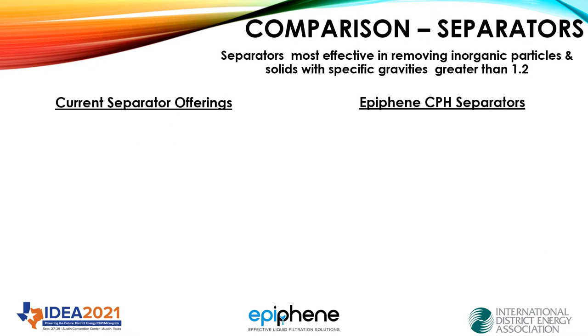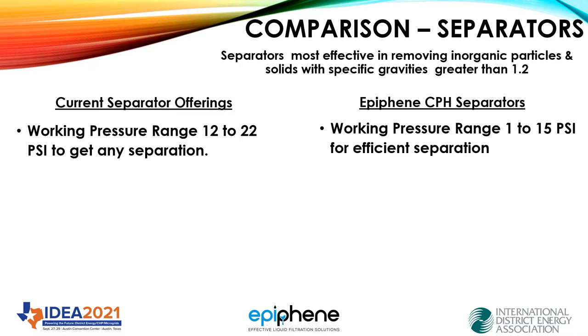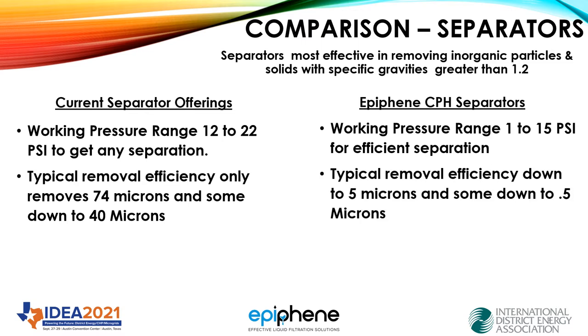So let's look at the comparison between separator technologies. Most effective in removing inorganic materials with solids that have specific gravities greater than 1.2, and in reality most of the separator companies start at 1.8 specific gravity. The working pressure range in terms of pressure loss is 12 to 20 psi to get any separation, whereas our working pressure range loss is 1 to 15 psi and we still get efficient separation. Typical removal efficiency is 74 microns and some down to 40 microns. Anything below 40 microns, you need really small separators to make that happen, and typically that's not done in the industry.